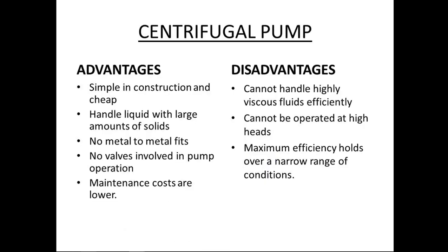Next, what are the advantages and disadvantages of the centrifugal pump. So first we take the advantages of the centrifugal pump. The main advantage of the centrifugal pump is its simple construction and cheap cost. It can handle liquid with a large amount of solids. There is no metal to metal fits in a centrifugal pump. No valve is involved in pump operation and maintenance costs are very low. These all are the advantages of the centrifugal pump.